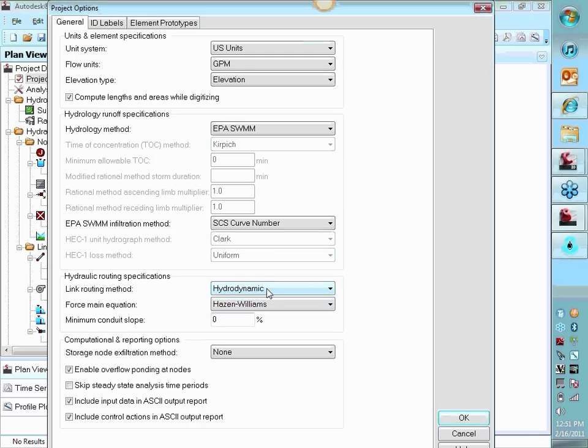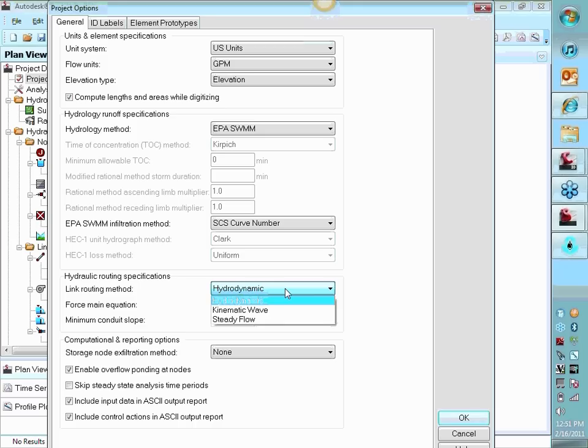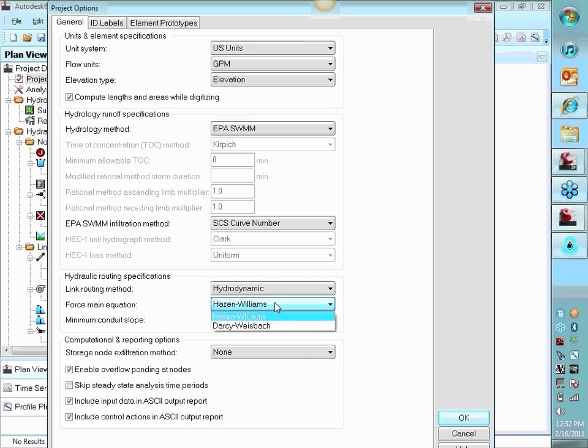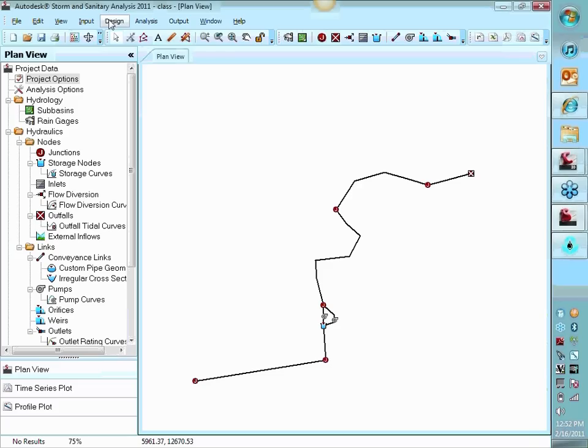Important piece down here is that when you are doing low pressure system design, you have to set this to hydrodynamic. If you have it set to kinematic wave or steady state, it's not going to let flow go both ways and it just won't run the model. Here we talked about the Hazen Williams and that's what we used. There's also the Darcy Weisbach for force main equation for when it gets pressurized.